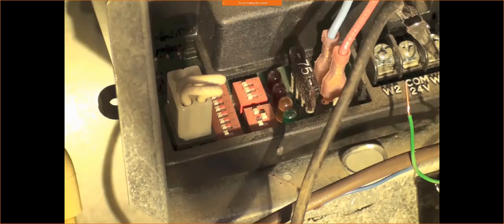It's going to try to restart. Maybe that first time something just got in the way, and it wasn't able to start. It could be an electrical issue, could be mechanical, who knows. The system's going to try 3 times. So that first time that it gets that error, it's a soft lockout. The board's going to know that the furnace didn't fire, something's up, let's try this again. It's going to try this 3 times. Some furnaces may just keep trying forever, depending on what the code is, but generally, after about 3 times, we're going to get what's called a hard lockout. That system's going to stop operating completely.